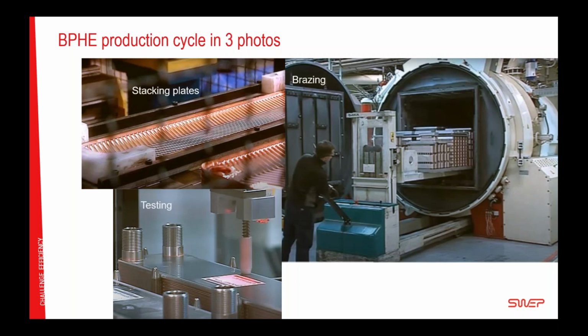If I'm going to show you how a braze plate is made, I'll show you 3 photos, and these are actually cutouts from an excellent SWEP movie on YouTube. So if you want to see the whole movie, go to SWEP's YouTube channel and search for what is a braze plate heat exchanger. But a braze plate is more or less pressing and stacking plates, as many plates as it needs to meet the customer's requirements. Then we put them in a furnace to bake them, and when they are done and they are hermetically sealed, we then test them and make sure that they are all right, and then we send them out.